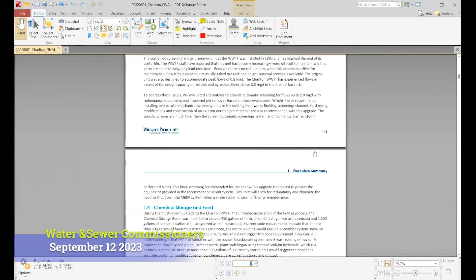Moving over to the chemical storage side of things, we did some process modeling of the system to determine that by adding automated soda ash to maintain alkalinity, we could potentially decrease the amount of sodium hydroxide that the plant had to keep and store on site.